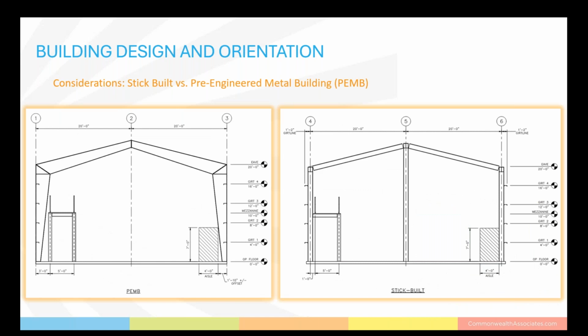In the previous slide, I mentioned stick-built versus pre-engineered metal building style. These two visuals highlight some of the differences between the two. Pre-engineered metal buildings use engineered columns that taper. The tapers can infringe upon the interior usable area of the building. Aisles, platforms, equipment, and pole space need to be placed far enough away from the base of the building columns so that they don't interfere with the building columns as they taper towards the roof. Often pre-engineered building manufacturers prefer that no other steel is hung from their columns or roof members without understanding all of the loads required. This forces the electrical and piping designers to have preliminary routes for tray, conduit, and pipe to be able to provide those loads to the manufacturer.